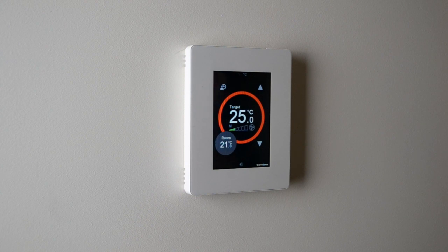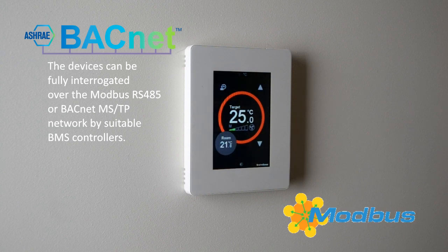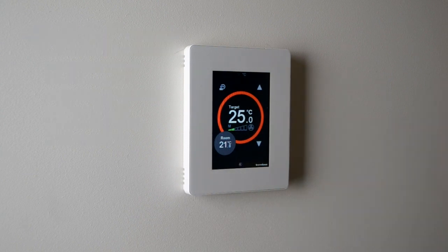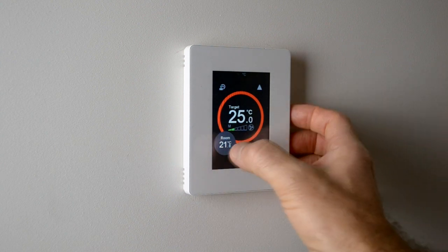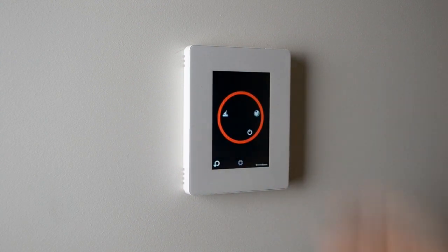You can connect these devices to Modbus and BACnet networks, and you can do all the settings and all the runtime operations over the communication networks. So they are really suitable devices for connection to BMS systems. Now, if I press the action ring again, I go to the second screen, where there's a little cogwheel icon that allows us to access the configuration settings.